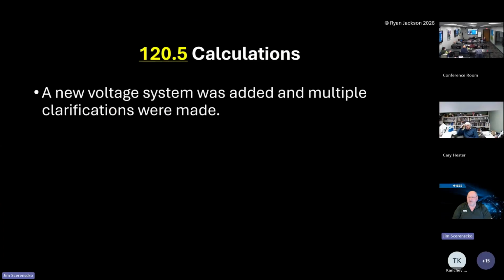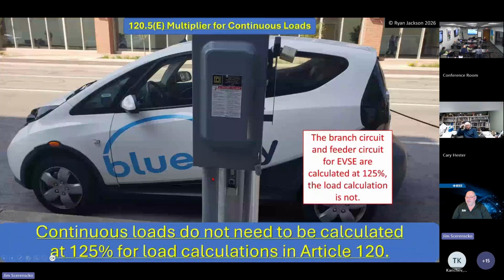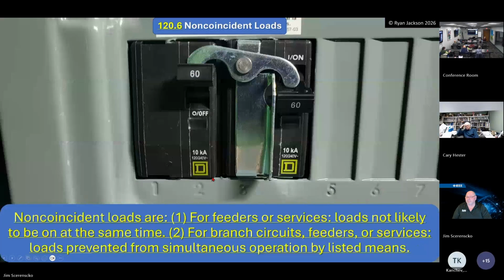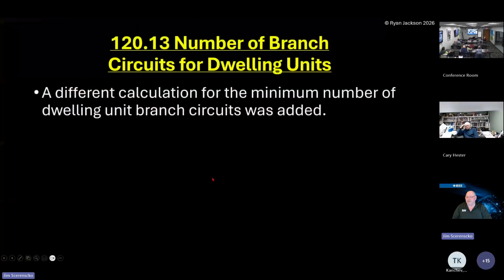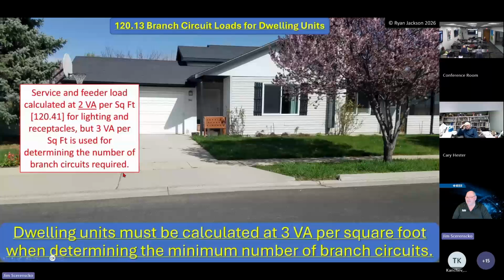There's something here I want you to be aware of, because if you're designing apartment buildings, multifamily, I don't know how everybody designs that stuff, but usually if you're doing a service calculation to size the service for a multifamily building, you take the square footage of the units times however many units there are, A, B, and C type units, come up with a total square footage, and then you go from there. There's a new calculation for sizing those dwelling units, because of the LEDs.